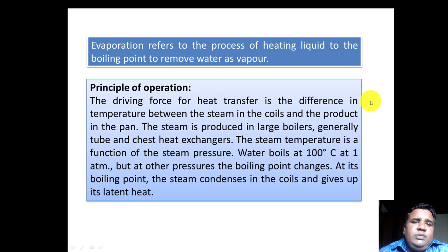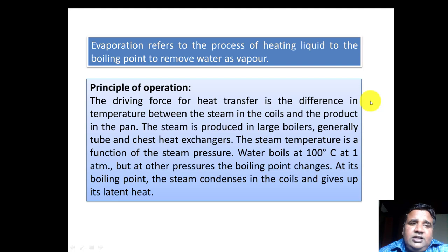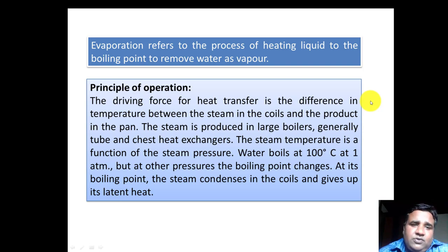What is the principle of operation of evaporation? The driving force for heat transfer is the difference in temperature between the steam in the coil and the product in the pan. For evaporation we generally take a material in a pan, and the pan is surrounded by coils in which a heating medium is circulating. The temperature difference between the heating medium and the product inside the pan is the main driving force.